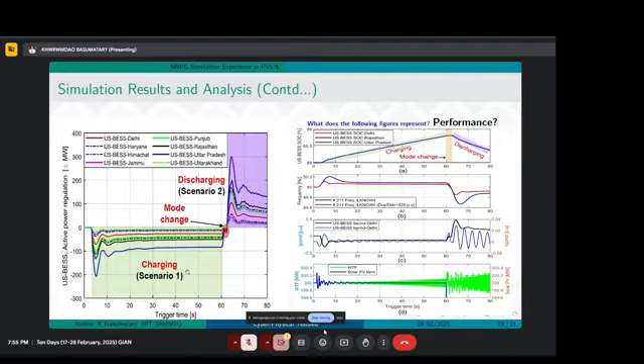These are the responses from the battery during the down frequency and up frequency events. During the down frequency event, the battery was releasing power, which is shown as negative — releasing power meaning compensating for the power, as when load was high when frequency was low.